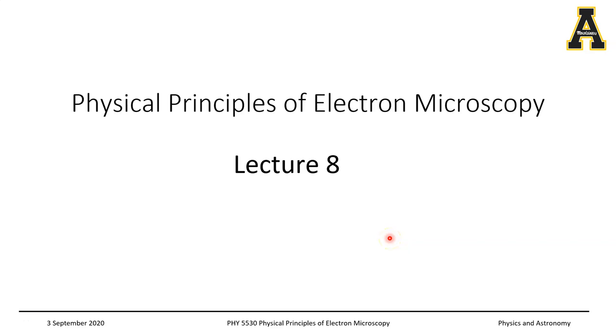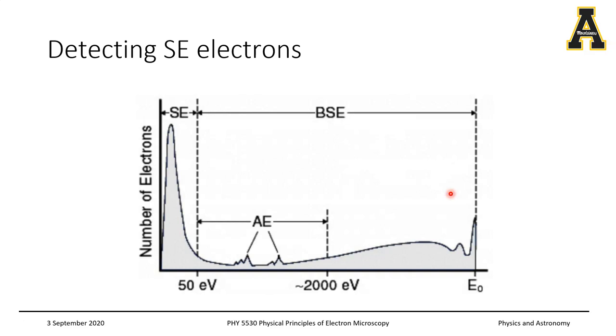Hello everyone, today we are going to continue from where we left off in the last class, where we were looking at backscattered electrons and how they can be detected using the solid-state detector. As a quick recap, if you look at the energy spectrum of electrons coming out of the sample, you have secondary electrons with energy less than 50 electron volts, and then a wide range of backscattered electrons generated from elastic scattering with energies all the way up to E0 — the energy of the incoming electron beam. The topic today is how we can detect these extremely low energy secondary electrons.